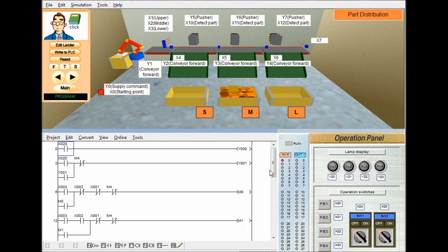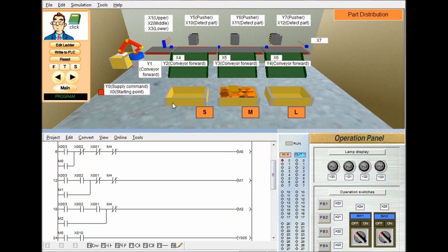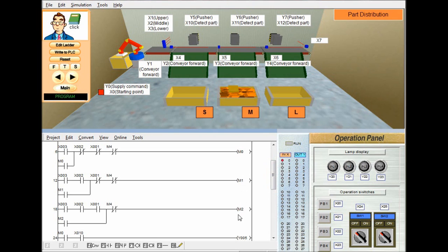When we press PB1, the robot arm places an object on the conveyor and the conveyor moves that object forward. The next three rungs — Rung 6, Rung 12, and Rung 18 — are used for memory function. When an object passes across sensors X3, X2, X1, the sensor output will be high. But when the object moves away, the sensor output goes low. So we have to memorize the output of these sensors to control the remaining conveyors and pushers. We use internal relays of Mitsubishi PLC, denoted by M — specifically M0, M1, and M2 for the memorize function.